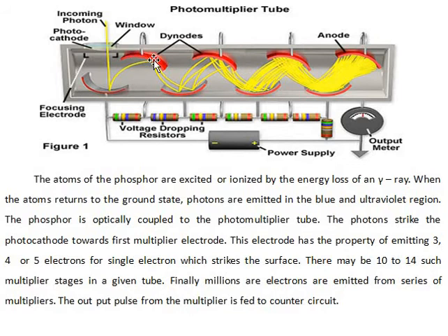These electrodes are arranged and their potential differences are set in such a way that for every interaction of the electron, they produce two or more photoelectrons. So that is the multiplication of the photoelectrons. At the end, a bunch of electrons is received due to one single gamma radiation interaction, so that it is counted. In this way, the scintillation counter is designed, dear students.